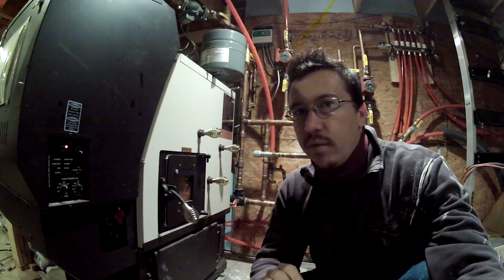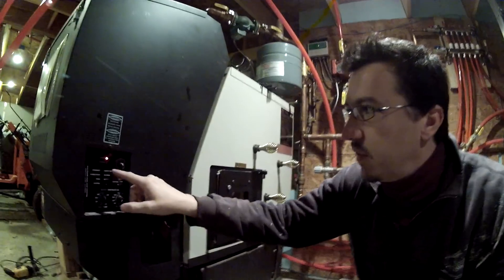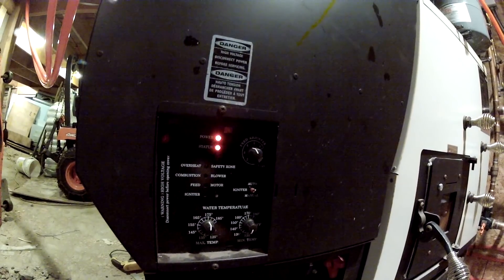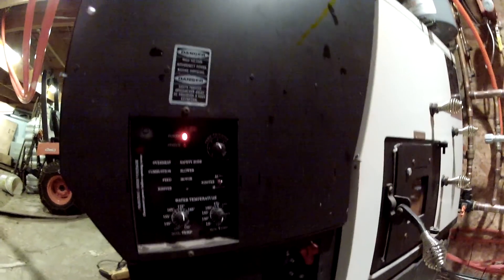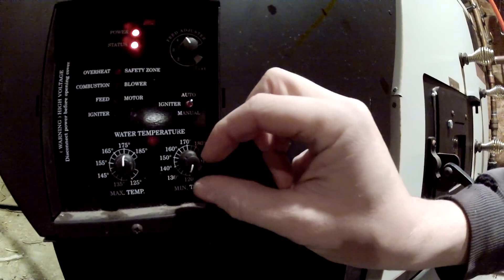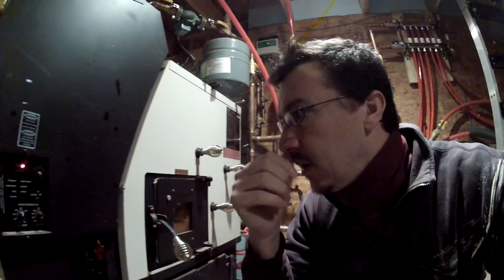One of the first problems I had with this boiler was the status light giving me a five-blink code. The way you reset it is just putting the min temp to off and then turning it back on — it resets and goes again. The code means the boiler could not fire for 40 minutes or more, so it stopped.